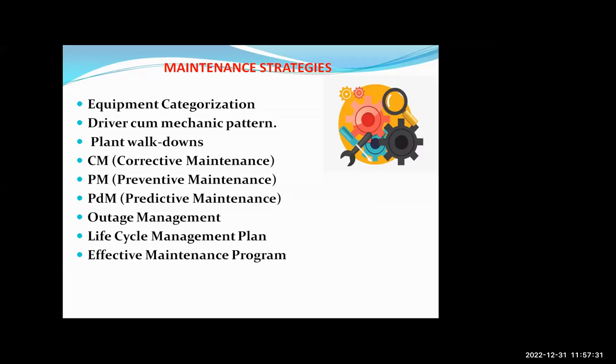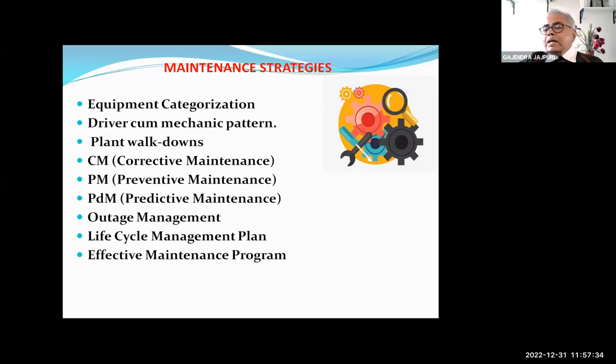Yes. So maintenance activities planned during a scheduled outage, whether due to mandatory requirement or power cut, need thorough planning. Suppose there is a weekly load shedding requirement and the small scale unit has to be shut down during that period. The planning has to be done so manpower is organized accordingly during that outage period, material has to be organized, spares have to be organized, and everything properly planned before carrying out the outage activities. This is a very big subject for a power station, because a power station outage usually takes about 30 days, during which the whole unit will not be generating power, and that period is allotted to the maintenance staff to carry out the outage work.